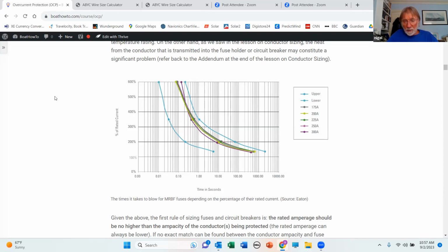And in practice, in terms of what's available in the marketplace, which is affordable and not too big and clunky, the next step up is a Class T fuse, which comes in a fuse holder about this size. They're typically maybe about $80. And a Class T fuse has an AIC rating of at least 20,000 amps. So for those larger installations, and for any significant lithium-ion installation, you need a Class T fuse in the circuit so that you've got that very high AIC rating. So for example, for a 1,000 amp hour bank at 12 volts, what kind of a Class T fuse would you suggest?